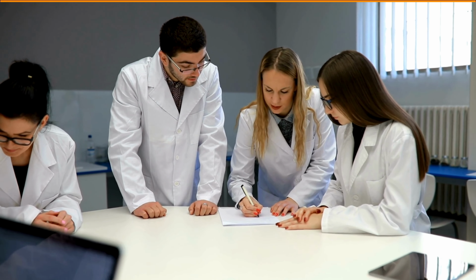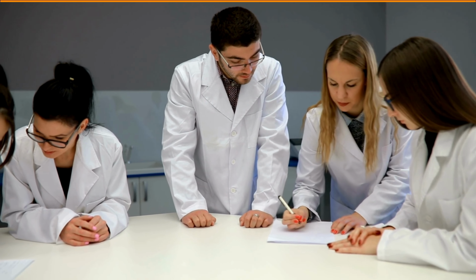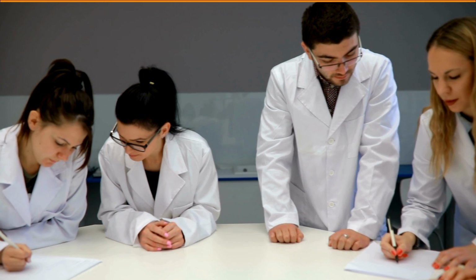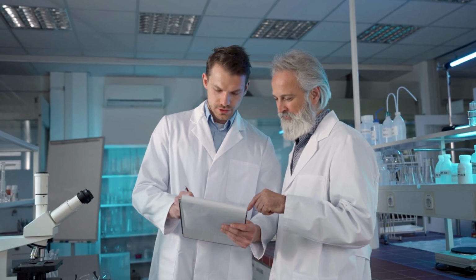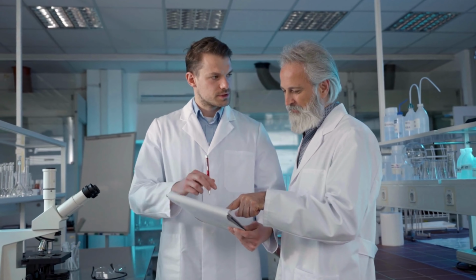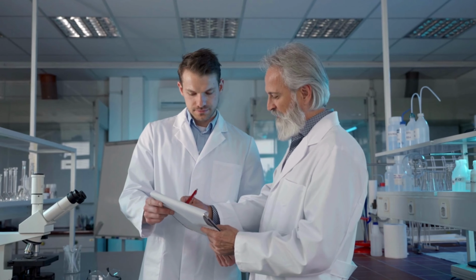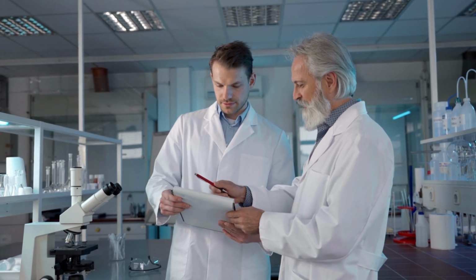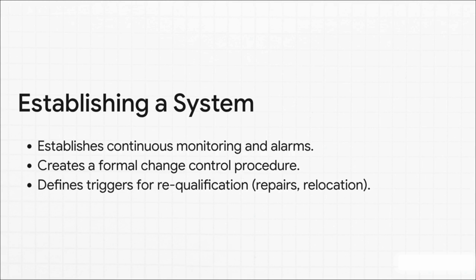But hold on, passing this test once isn't the end of the story. This is not a one-and-done kind of deal. It's really a living, breathing process of trust and verification. A successful qualification doesn't just give you a thumbs up for that moment. It sets up a whole system for the future. You establish things like continuous monitoring and alarms. You create a formal procedure for how to handle any changes, and you define exactly what would trigger a full requalification, like a big repair, a modification, or even just moving the freezer across the room.